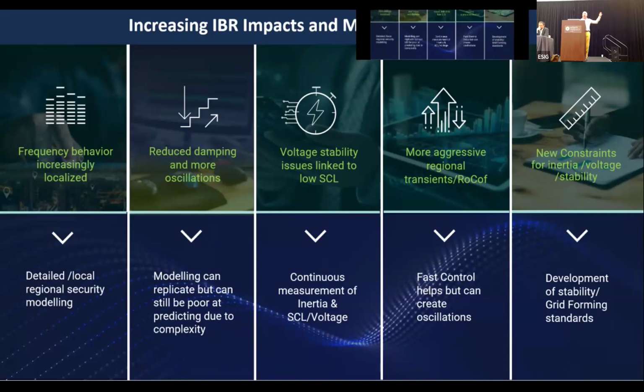Fast control, grid forming, and very fast frequency response - sub 2 seconds, typically 500 milliseconds - is brilliant, and plays a major role in containing these issues. But you've got to start thinking about the power system fundamentally as an oscillatory system, like a physical system that vibrates and has its own resonances.